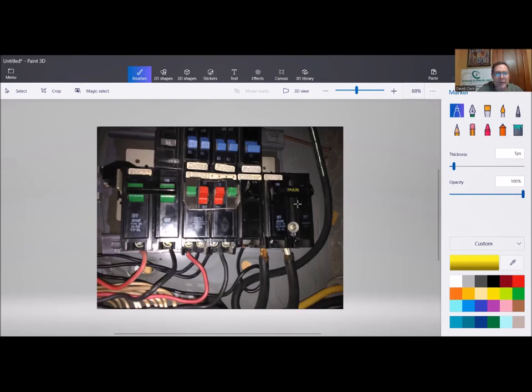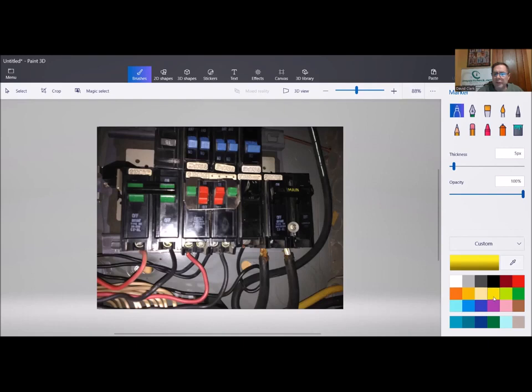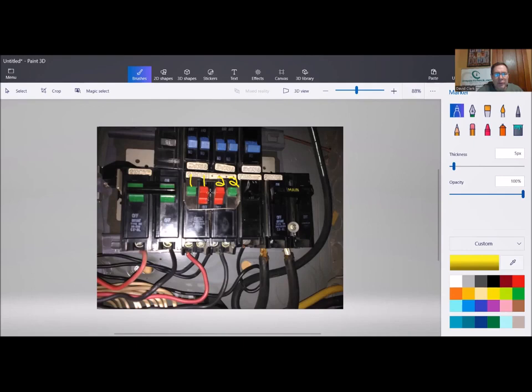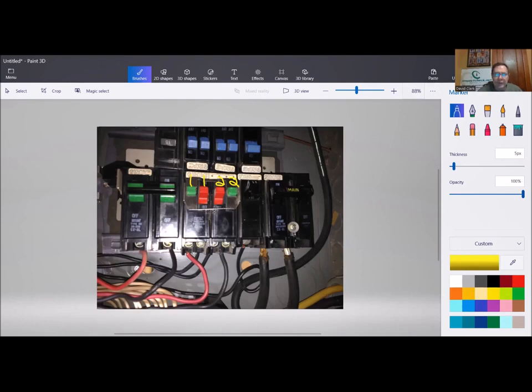All right, so let's take a look at how this breaker works. In this case, we've got one 240 volt circuit and two 120 volt circuits. Let's take a look. And if we look here, we're on opposite sides of the pole. So we have 120 on one side, 120 on the other. This is one side or left side or right side, and then this is the other side. So we can't make a 240 volt circuit out of these two, the green and red. The color coding helps flag that. We can't do that because we're only at 120 volts here, we have to pull from the other side. This is why this is configured this way.